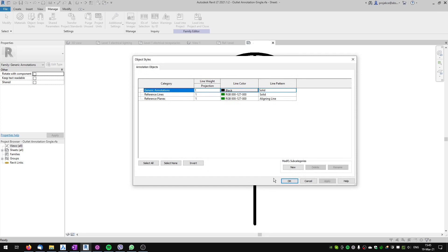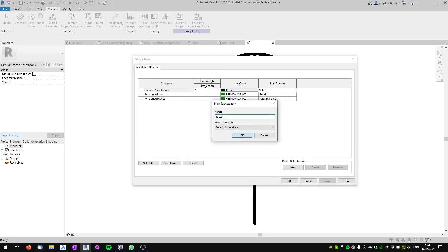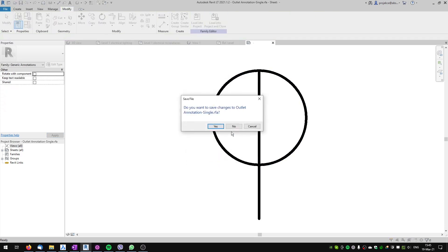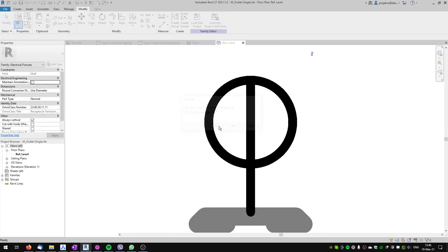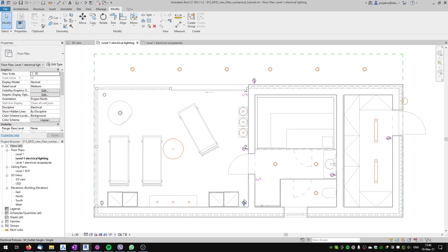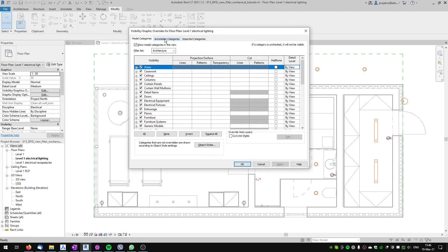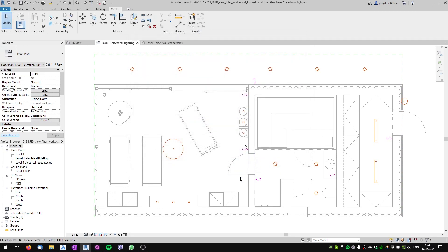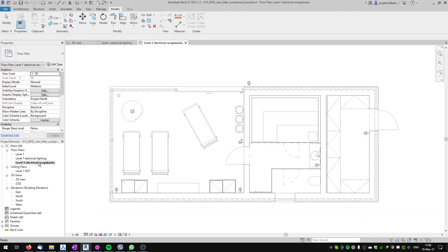I'll save the receptacle family to the desktop, go to the floor plan, select the symbol, edit the nested family, go to Manage, create a new subcategory named 'receptacles'. I'll select all the lines and move them to the 'receptacles' subcategory, load it into the outlet family, override the existing version, and load into the project. Now in Visibility Overrides, annotation categories, generic annotation, I can untick 'receptacles' in the lighting plan. The receptacles are no longer visible in my lighting plan, and switches are not visible in my receptacle plan.